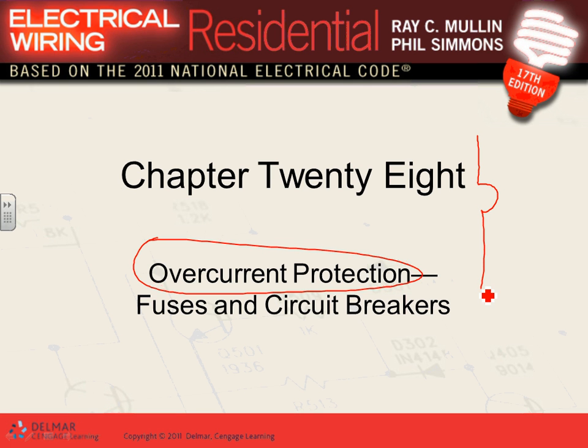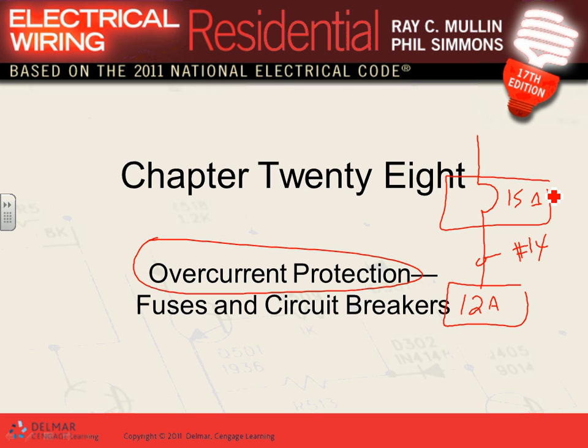You have a circuit breaker, like a 15-amp circuit breaker, and you're pulling 12 amps out of that load on a number 14 conductor. The NEC requires you, before you feed this 12-amp load at any voltage, to protect the conductors as well as the equipment from an overcurrent condition.